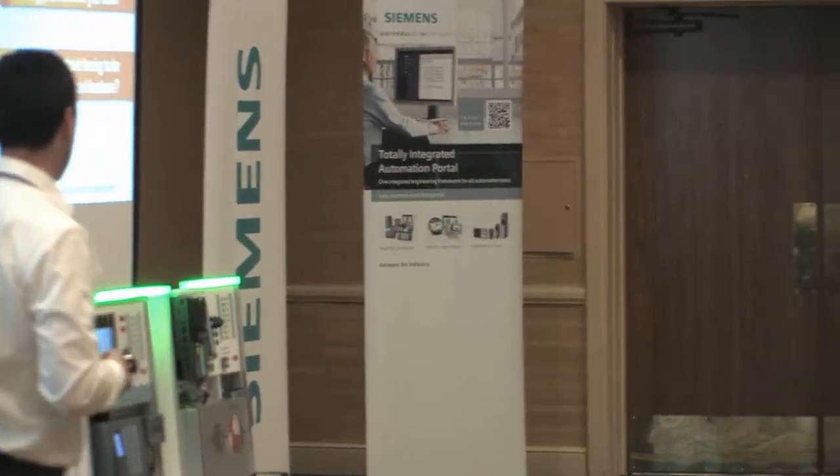Jeremy added: the comfort panel supports both PROFINET and Ethernet/IP and can act as a gateway for data transfer between Siemens and third-party solutions. The S7-1500 also supports Modbus TCP — an open platform supported by many third-party products — at no extra charge. You also have raw UDP or TCP sockets, so even a barcode scanner spitting data to a TCP port can feed directly into the S7-1500. There are multiple ways to interface even without PROFINET support.